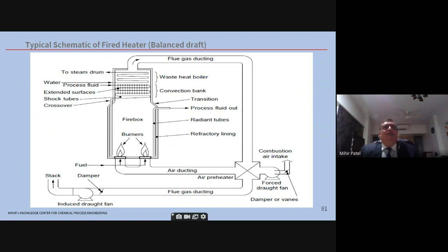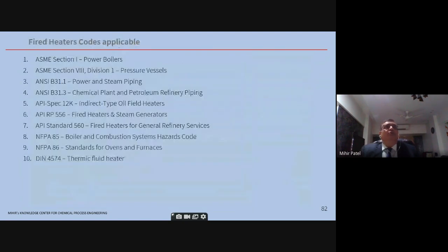The shock tubes are below the convection section. The three bottom tubes are called the shock tubes. They are not finned. Above that starts the finned section, which is the convection section. And above that, you can also have a preheater for the water. Finally, the flue gas ducting goes into the APH and out through the ID fan. So this is a balanced draft assembly. This gives maximum efficiency.